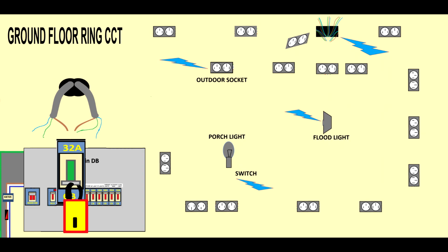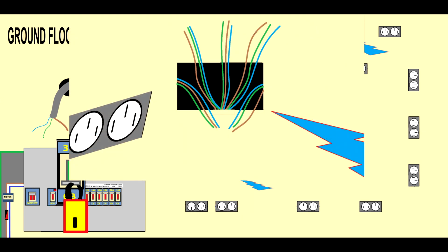But the problem is I opened another socket and wow, I couldn't believe I had 5 cables in that socket. Then I said, oh my god, this is a junction box. And then I had to open the rest of the sockets and sound out the wires to see where each one goes. I had to configure the circuit somehow in my mind. And towards the end I found the fault. It was in a wall somewhere.